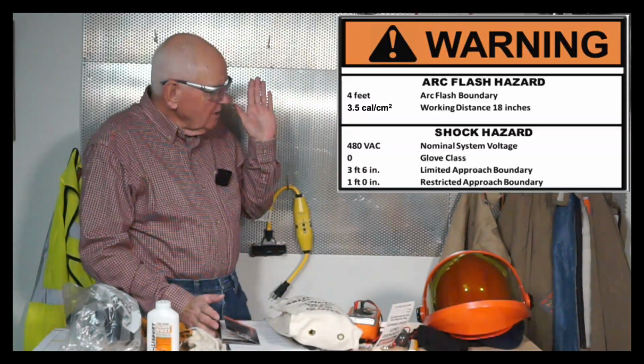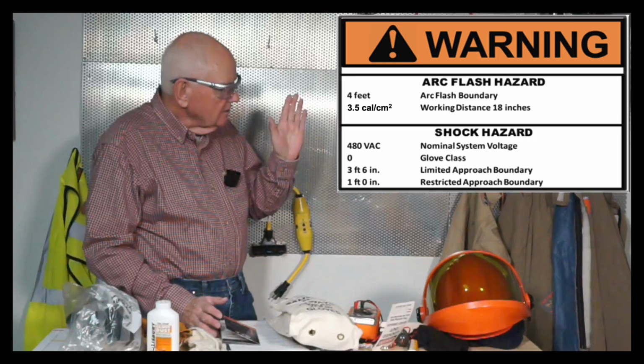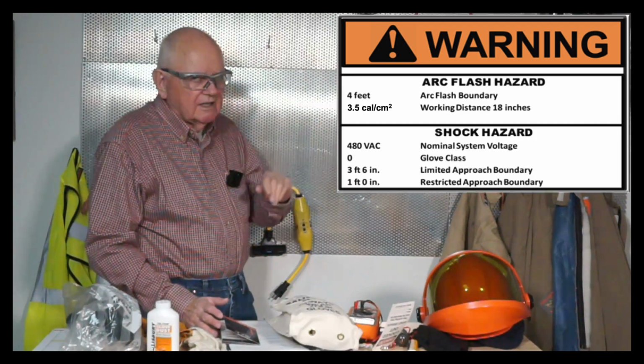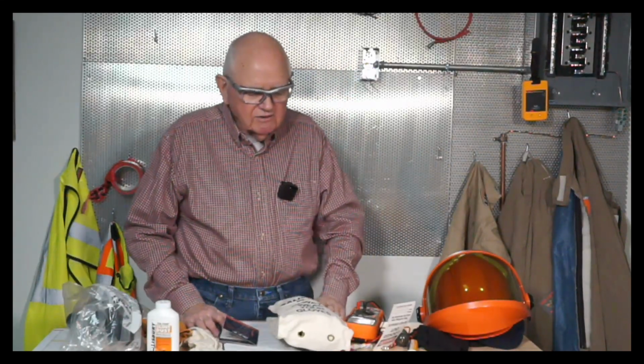So we select the proper PPE. The next thing that we're going to do is we want to set up the barricade where we need to. On that label, it gives us the limited approach boundary, the restricted approach boundary, and then the arc flash boundary. The limited approach boundary we said is for shock protection. For 480 volts, that comes right out of the tables, whether I'm using 70E or OSHA or whatever. Right out of my tables, 480 volts is going to be 42 inches, right? So 42 inches, I need to keep unqualified people back 42 inches for shock protection. 12 inches, I don't want to get any closer than 12 inches unless whatever I have is insulated.